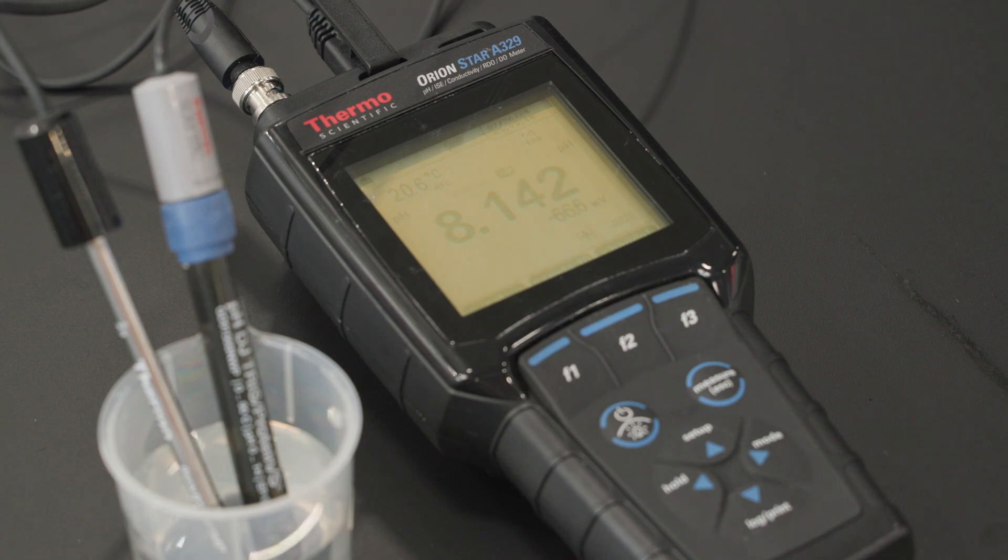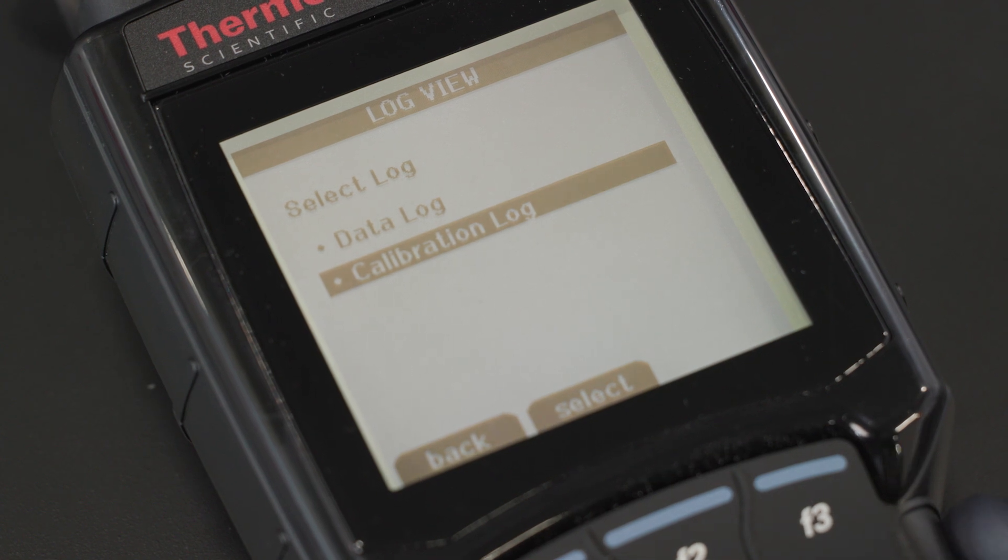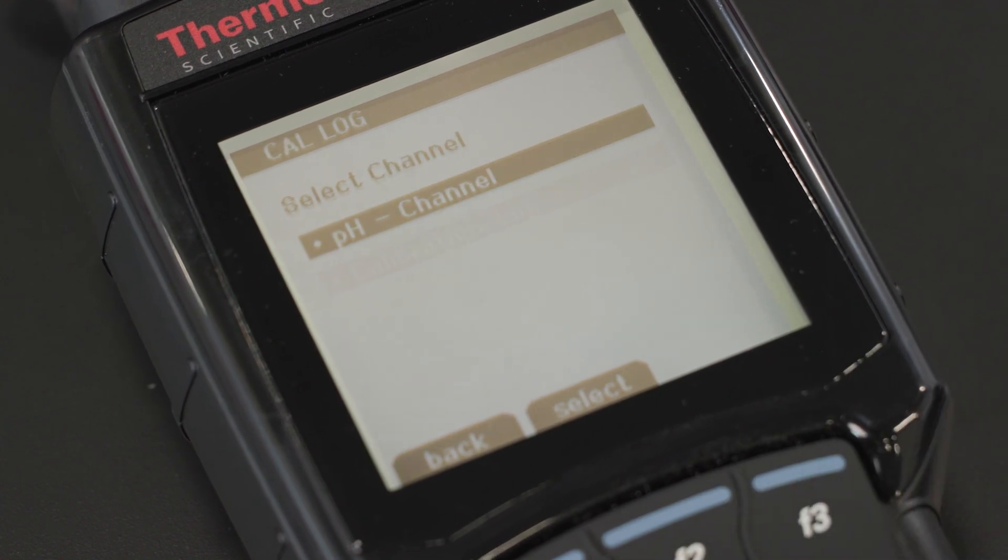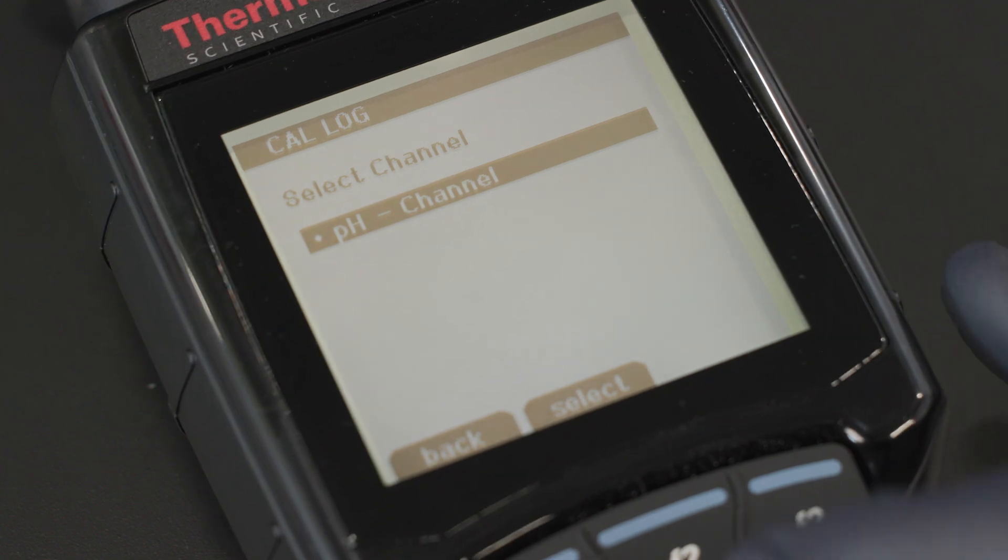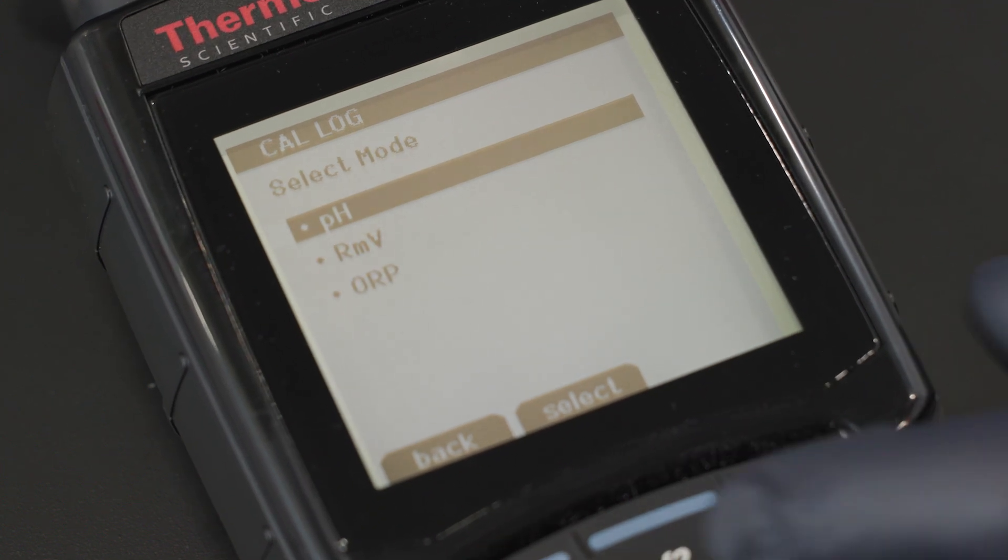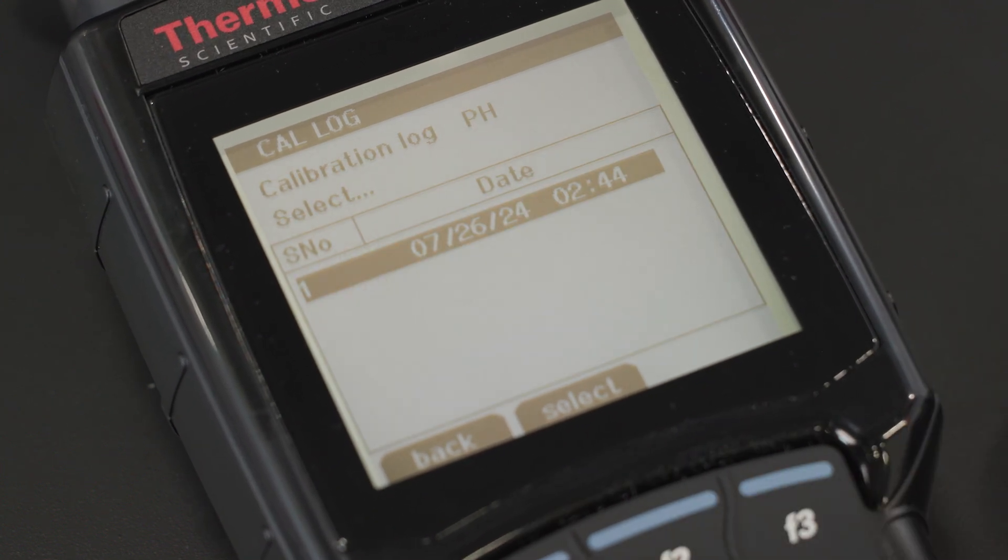The calibration log keeps a record of calibration details such as dates, times, calibration standards, measured values, and calculated values. It provides a traceable record for quality control and compliance purposes.